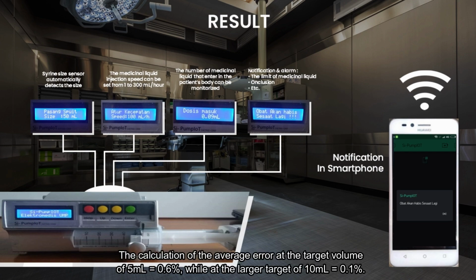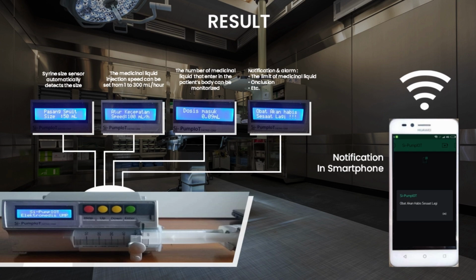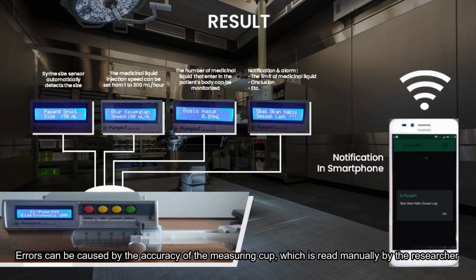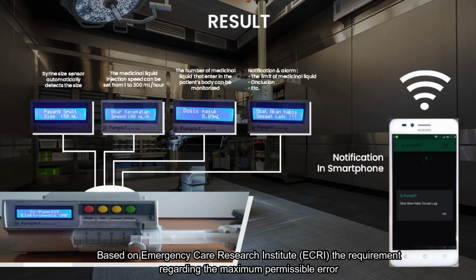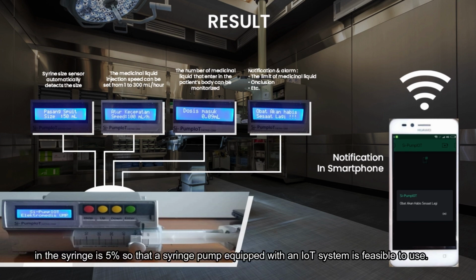The calculation of the average error at the target volume of 5 ml is 0.6%, while at the larger target of 10 ml it is 0.1%. Errors can be caused by the accuracy of the measuring cup, which is read manually by the researcher. Based on the Emergency Care Research Institute (ECRI), the requirement regarding the maximum permissible error in the syringe is 5%, so that the syringe pump equipped with an IoT system is feasible to use.